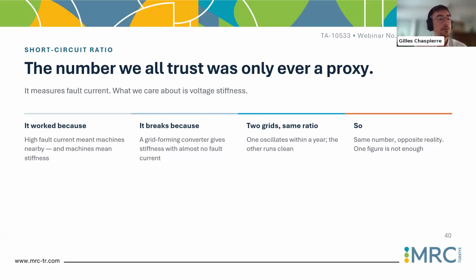So why was it useful when the system is dominated by synchronous generators? Well, simply because classic synchronous machines, as has been said previously, can provide high fault current. And so if you have a high short circuit ratio, it means you have in the vicinity high fault current, and direct translation, you have in the vicinity a sufficient amount of synchronous generators, so you know that your grid is strong, because synchronous generators, as mentioned, bring fundamental inertia, fundamental voltage control, and short circuit current capability in your system. But the problem is the following.